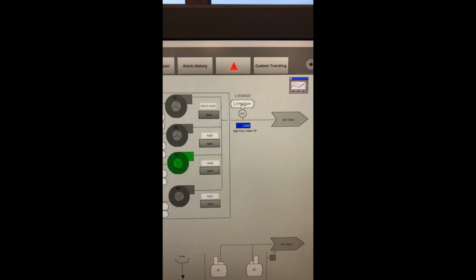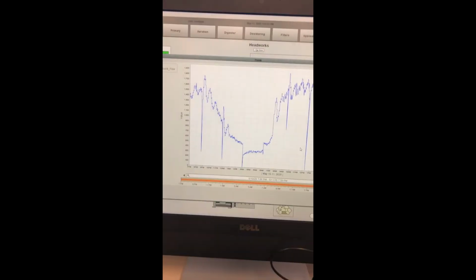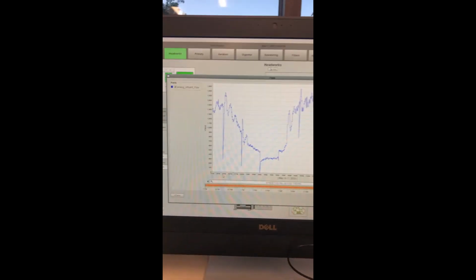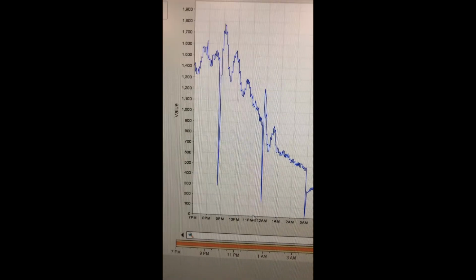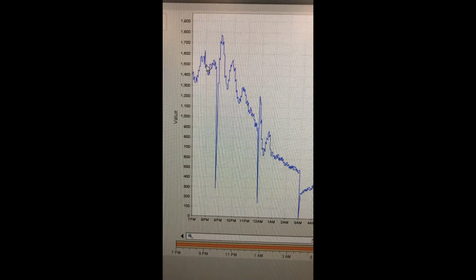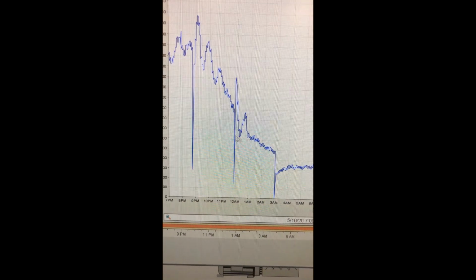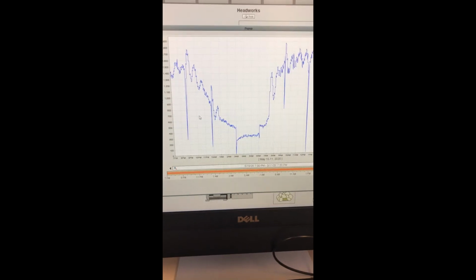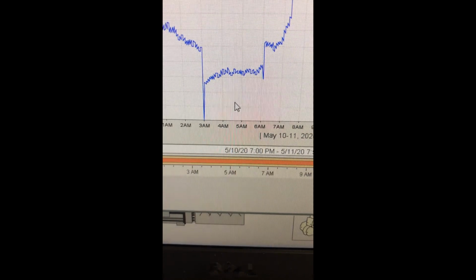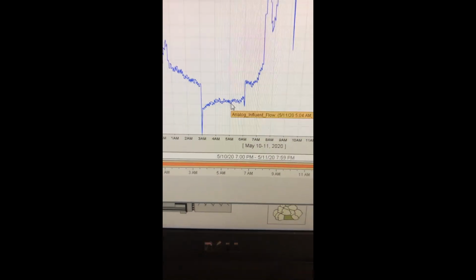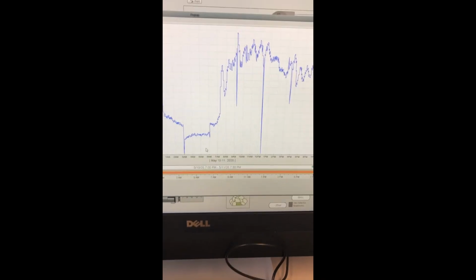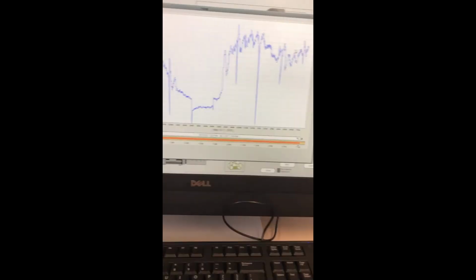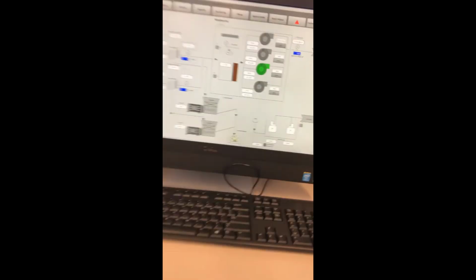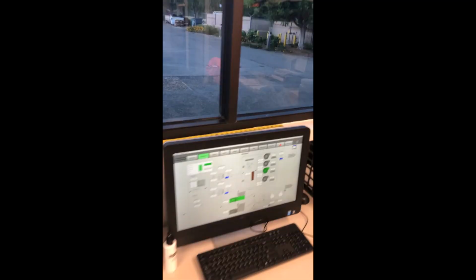Here's the influent flow. We'll double click it. You can see the flow coming to the plant is very diurnal. Looks like about 9 o'clock at night is when we see our high flow here. These spikes that you see, where it's going up and down, that's just when the pumps swap duty. They go off and on briefly. That's all that is. And you can see, about 3-4 o'clock in the morning, we got very little flow coming to the plant, and everybody wakes up in the morning and look at all the sewage coming to us. So again, that's just a graphical illustration of what's happening to the plant.